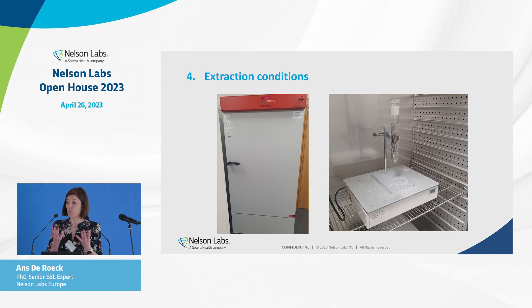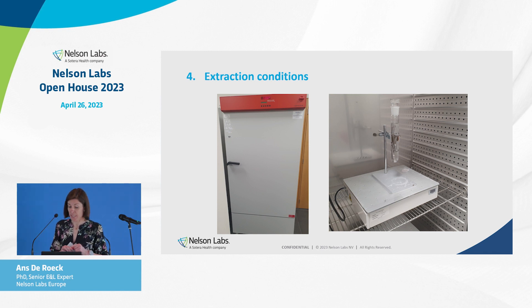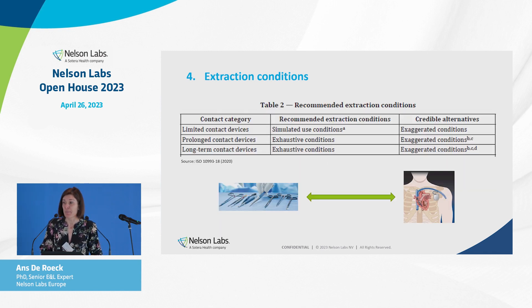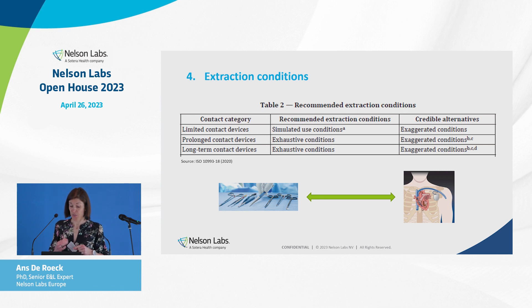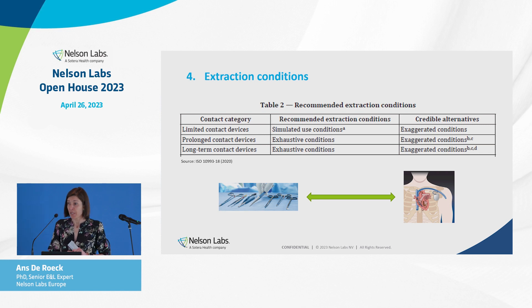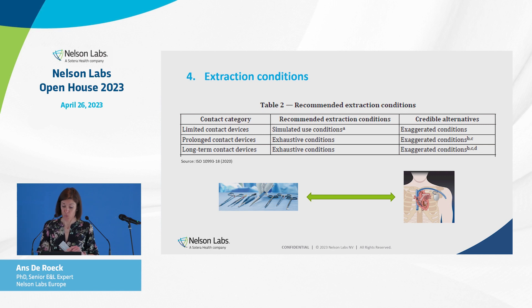The next step is incubation for a certain time at a certain temperature, mostly under shaking conditions in an incubator. Part 18 includes a table with recommended extraction conditions or credible alternatives depending on the contact category. These range from a simulated-use condition to an exaggerated condition or an exhaustive condition. A typical exaggerated condition we use is 50°C for 72 hours.